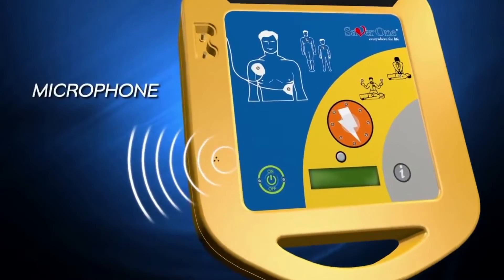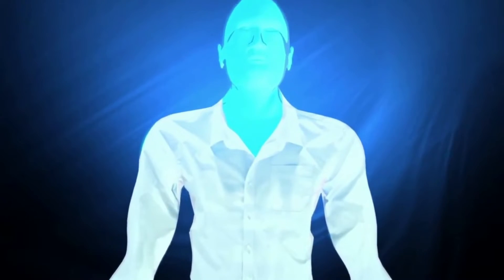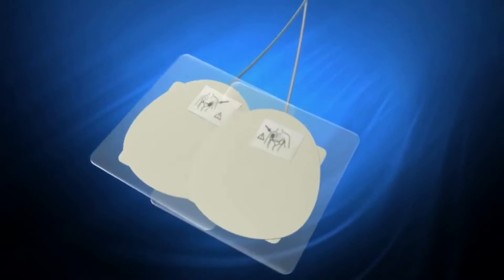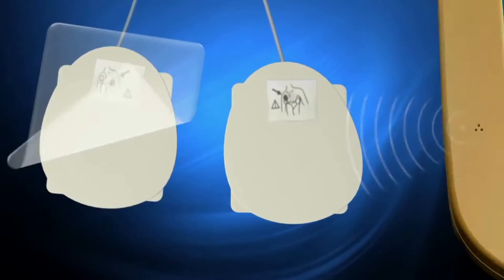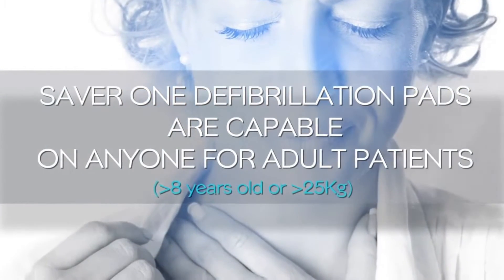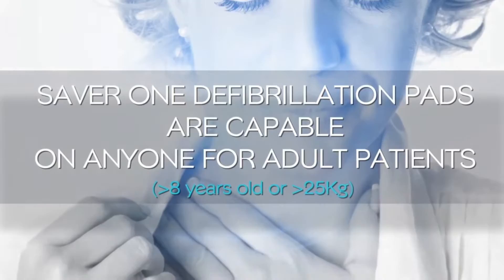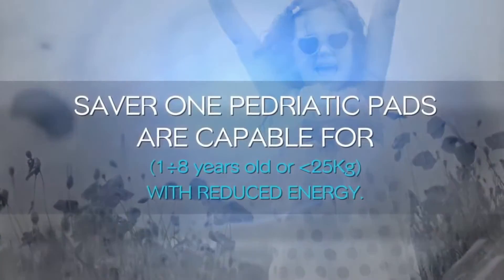Stay calm and follow these voice instructions. If the patient is unresponsive and not breathing, loosen or remove clothing to expose the bare chest and apply the electrodes. Open the package and look carefully at the picture on the electrodes. Peel electrodes from the plastic liner. Adult defibrillation pads are suitable for patients over eight years old or weighing more than 25 kilos. Saver One pediatric pads are suitable for ages one to eight years or weighing less than 25 kilos, with reduced energy.